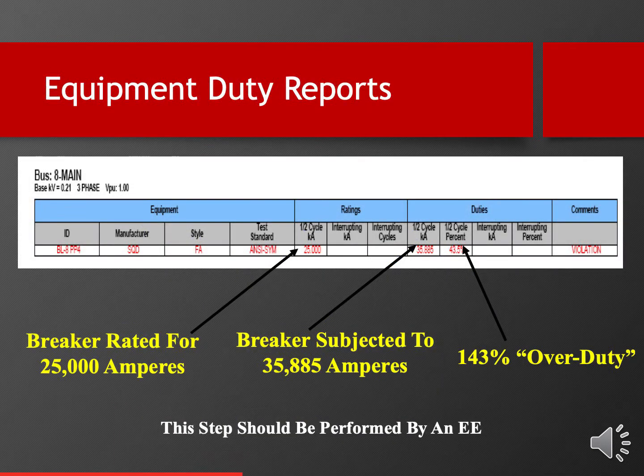What you see here, most arc flash calculation software have some version of this. The software we use calls this equipment duty. And equipment duty compares the interrupting rating of a protective device to the actual short circuit current to which it will be subjected. And this is so important because we never knew this when I used to do the work. But there are a number of devices, especially if you work in an older facility, that may not be able to interrupt the current flow to which they're subjected. And if you were to reset that breaker now, it would likely result in something called a through fault, which would probably result in an arc flash event.